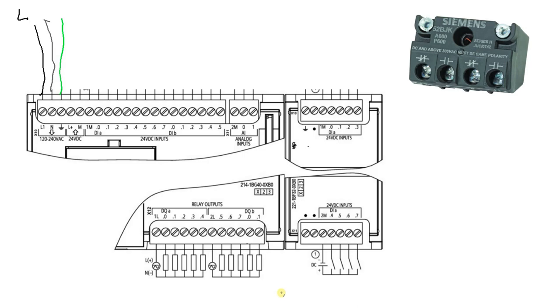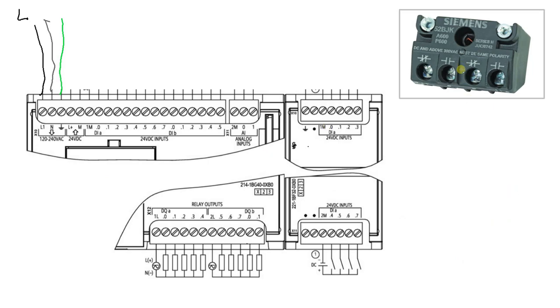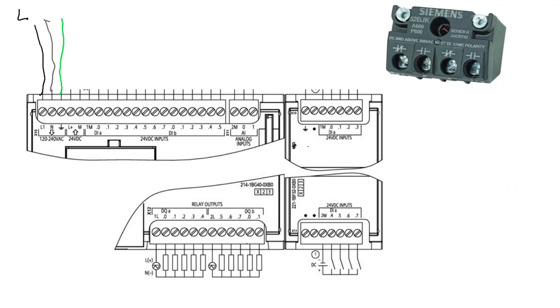Now that we got our line neutral ground hooked up to this PLC, we can turn it on if we want to, but for all intents and purposes, we're going to continue on to how to wire up that switch off to the right here. The first thing before we get these digital inputs wired up, we need to get a common back to our power supply. Since we don't have a power supply and I don't want to put one on the screen, I'm going to use the power supply that's on the S7-1200.